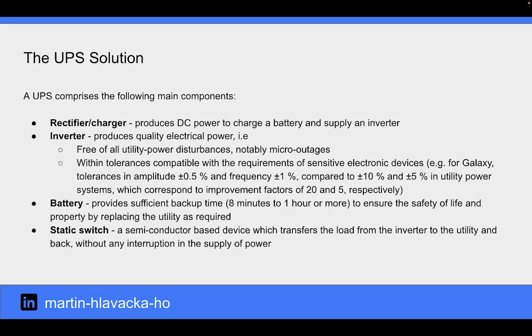A UPS comprises the following main components: a rectifier that produces DC power to charge a battery and supply an inverter, an inverter that produces quality electrical power free of all utility power disturbances and within tolerances compatible with the requirements of sensitive electronic devices, a battery that provides sufficient backup time to ensure the safety of life and property by replacing the utility as required, and a static switch, a semiconductor-based device that transfers the load from the inverter to the utility and back without any interruption in the supply of power.